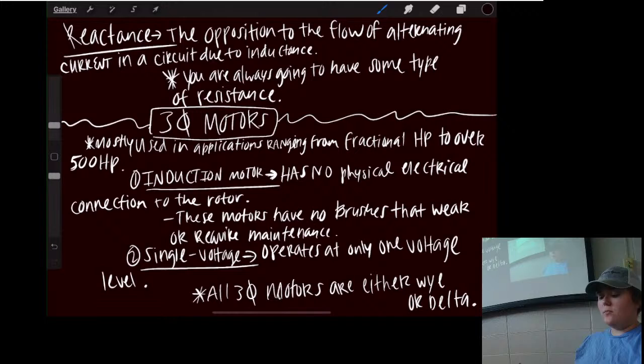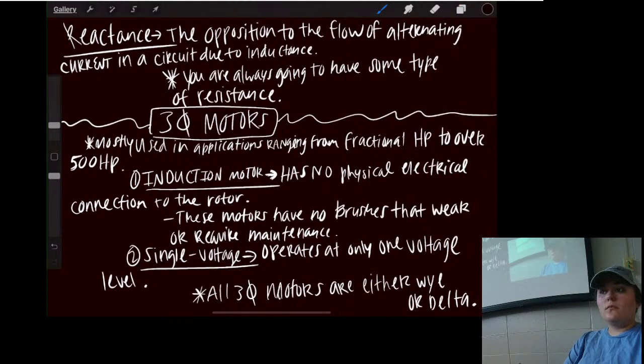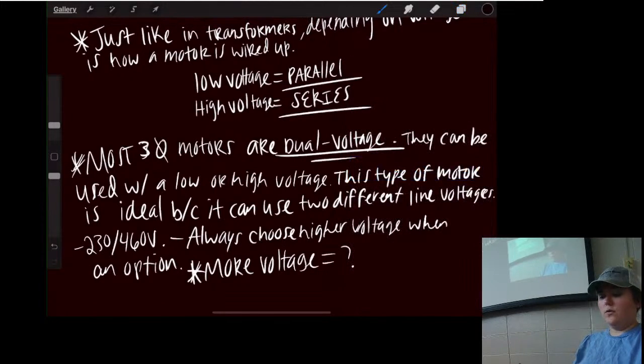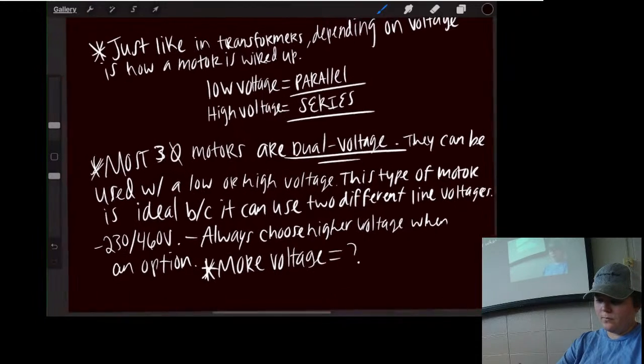All three-phase motors are either Y or delta, and that's something to remember. If you're working with a three-phase motor, it's either going to be in Y or delta, period. Those don't switch. So single voltage motors don't switch configurations - if you've got single voltage, you're either going to have a Y or a delta. So the smart thing to do is buy a dual voltage motor.